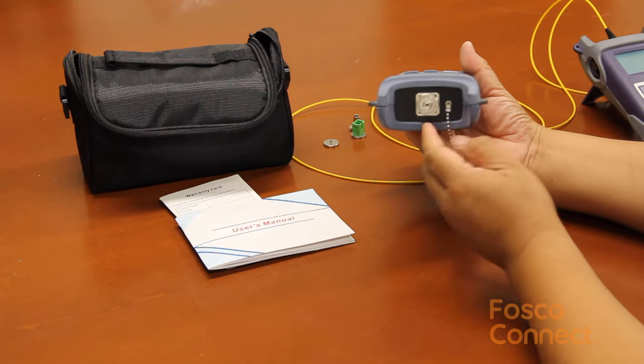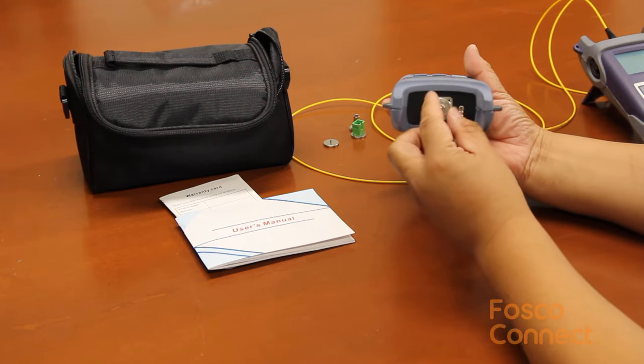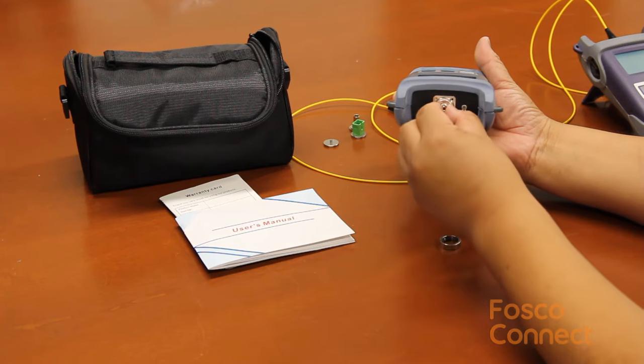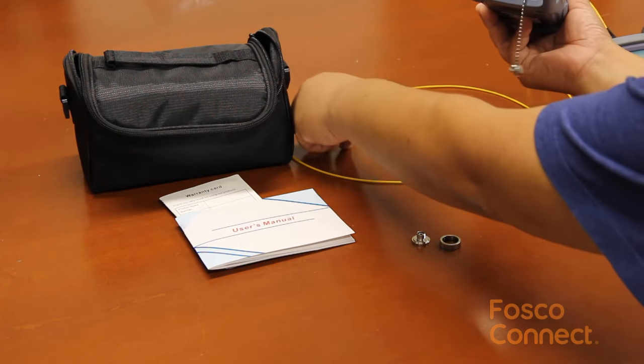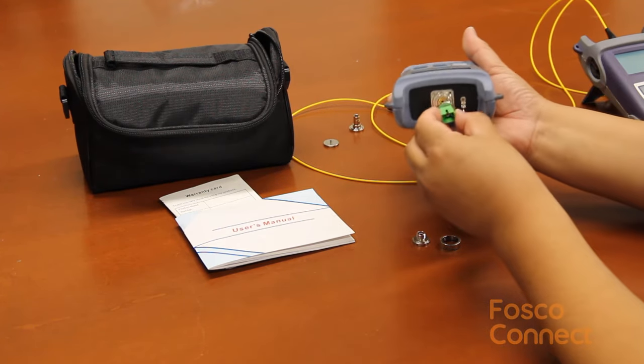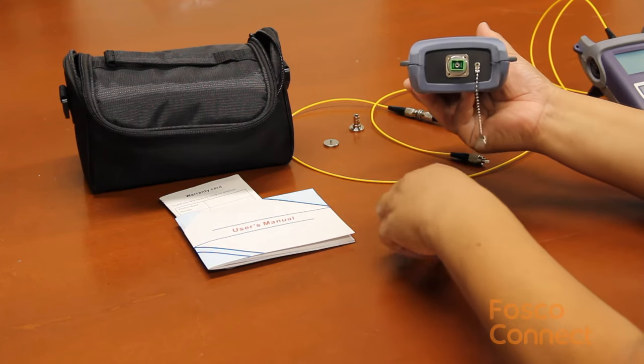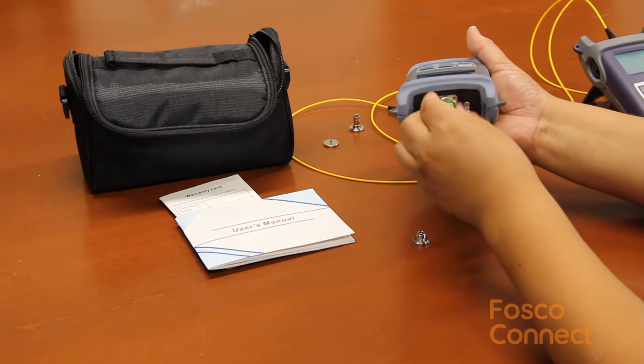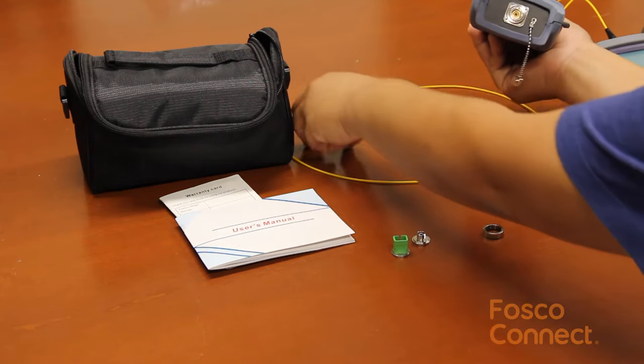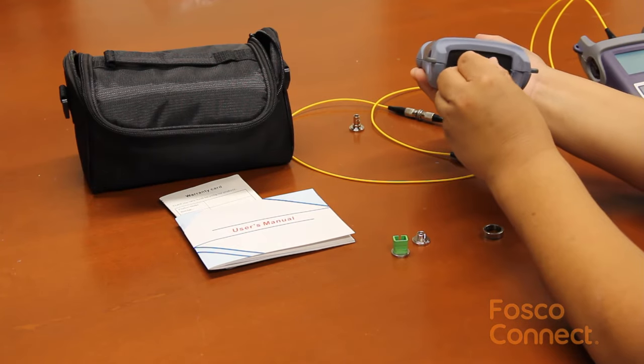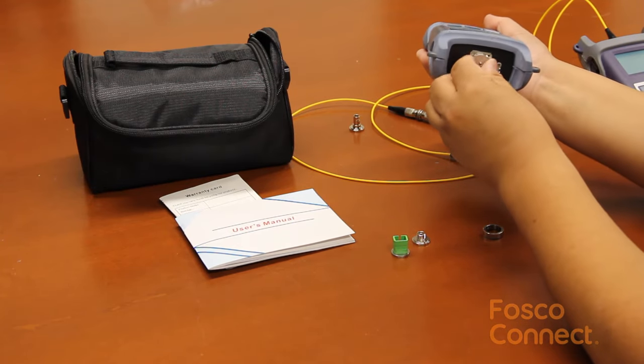The power meter has an interchangeable adapter. We can take it out and change to SC APC adapter. We also have LC adapter to measure LC patch cables.